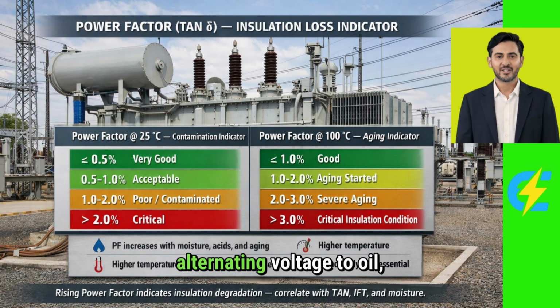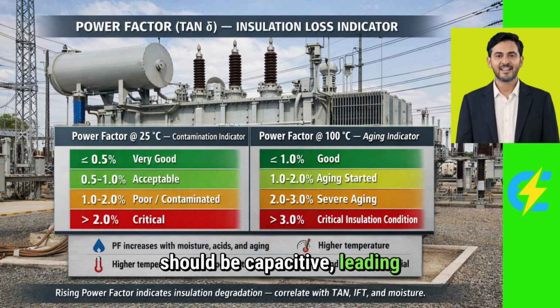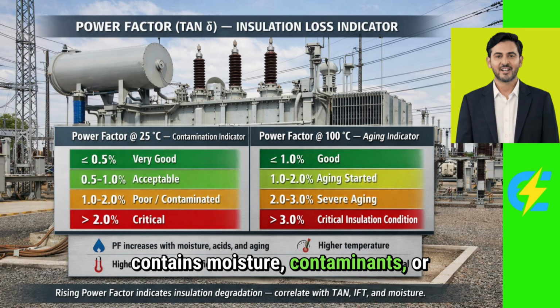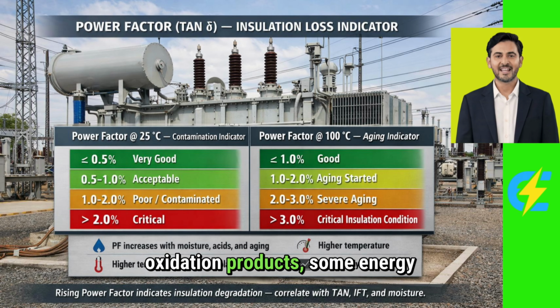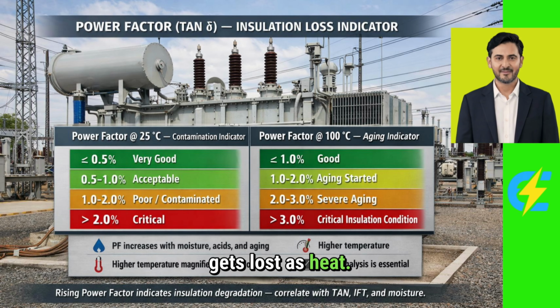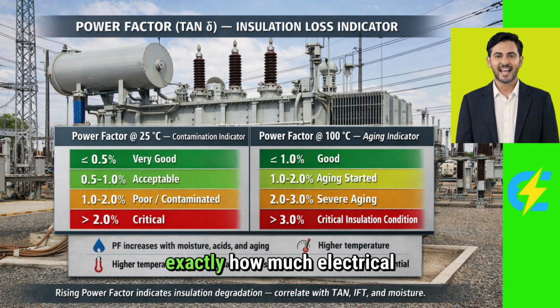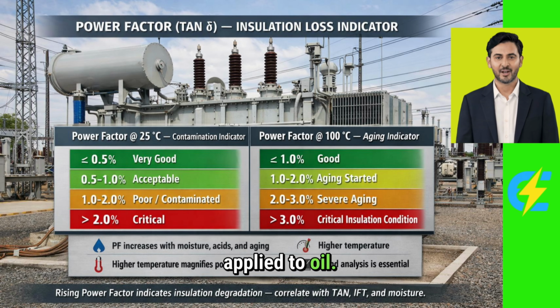When you apply an alternating voltage to oil, ideally all the current should be capacitive, leading the voltage by 90 degrees. But when the oil contains moisture, contaminants, or oxidation products, some energy gets lost as heat. Power factor tells us exactly how much electrical energy is lost as heat when voltage is applied to oil. It's measured as per IEC 60247 and ASTM D924 standards.